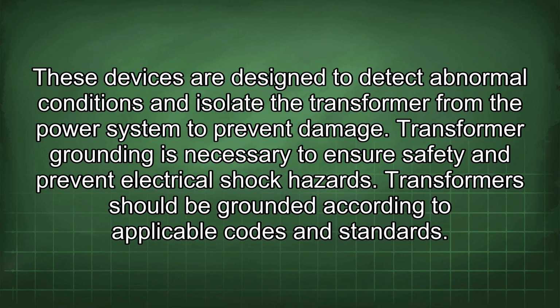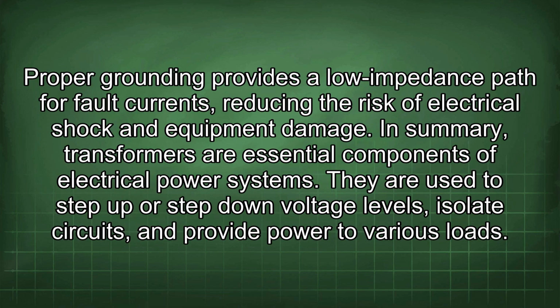Transformer grounding is necessary to ensure safety and prevent electrical shock hazards. Transformers should be grounded according to applicable codes and standards. Proper grounding provides a low impedance path for fault currents, reducing the risk of electrical shock and equipment damage.